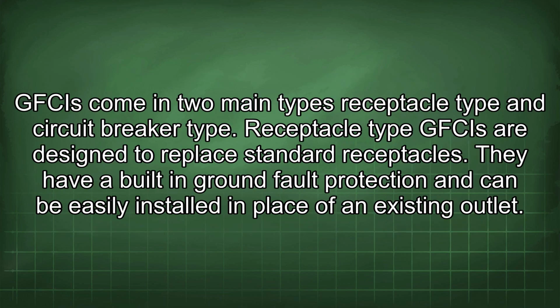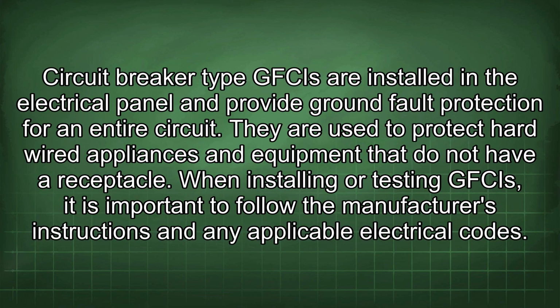GFCIs come in two main types: receptacle type and circuit breaker type. Receptacle type GFCIs are designed to replace standard receptacles. They have a built-in ground fault protection and can be easily installed in place of an existing outlet. Circuit breaker type GFCIs are installed in the electrical panel and provide ground fault protection for an entire circuit. They are used to protect hardwired appliances and equipment that do not have a receptacle.